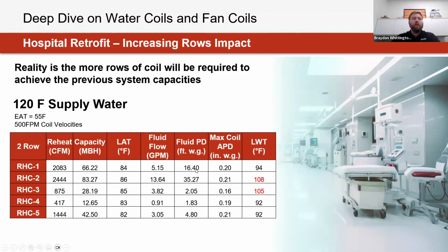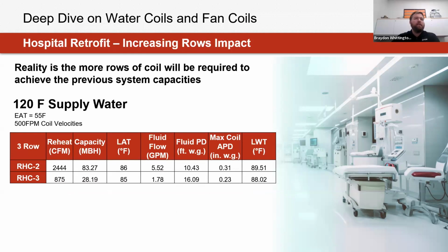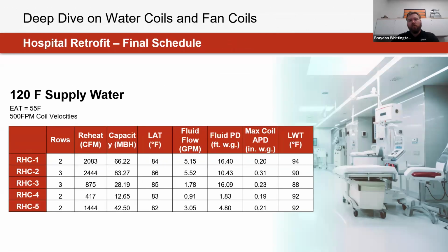And that's one consideration that we're going to have to take into account. But then also the consideration that the air pressure drop of this coil is starting to get really close to that 1/4 inch that was initially laid out. So if we were to try then for those 2 remaining tags that were not quite there, what we'll see is that now these are also able to achieve those capacity targets that were initially laid out, but also now at a higher fluid pressure drop, so just above 10 or around 15, for those existing coils, and then also slightly above for some of them that 1/4 inch water gauge target of air pressure drop from that coil.